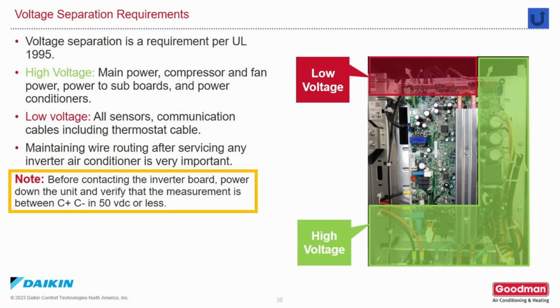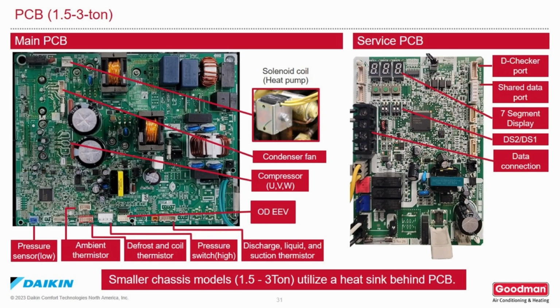So before touching the inverter board, make sure that you power the unit down, give it a few minutes for the capacitors to drain, and then measure voltage between terminals C positive and C negative and ensure that it's less than 50 volts DC. Here is an example of a main control board and the service control board in a 1.5 to 3 ton outdoor unit.